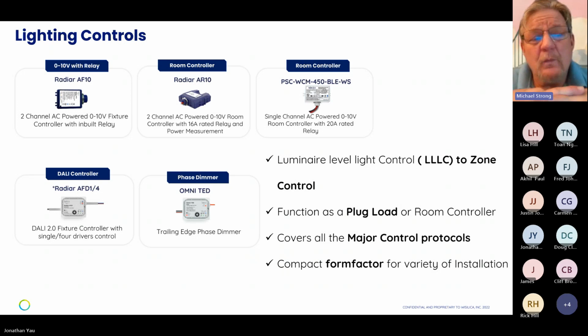Having an AF10 in each individual light allows you to separate the lights into zones depending on where they are located within a primary zone. So an office space may have daylight and secondary daylight zones, and being able to control those lights only within that zone becomes really simple when you have an AF10 in each fixture.